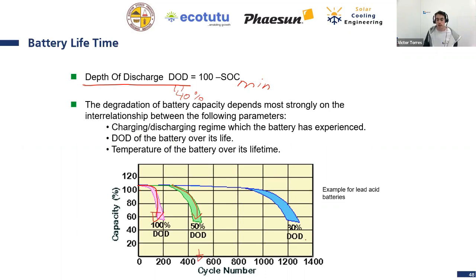If you discharge only with 30% DOD, discharging to a minimum SOC of 70%, you will have a longer lifetime, up to 1,200 cycles, which is 4 years, 5 years, and so on. This is also a design question. We know how much energy we need in the batteries to run our system, but it's our decision if we buy a bigger battery and use a smaller DOD, or have a small battery and use a higher DOD. Depending on this, we have to replace the battery more or less often. I hope this is clear for you.